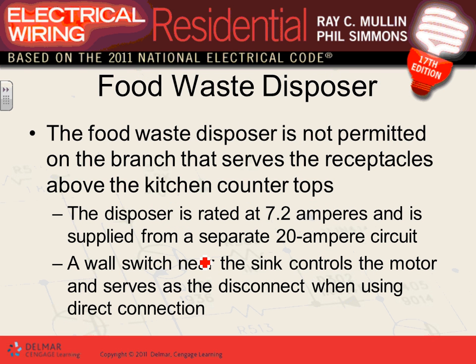Okay. Food disposal. Here's a typical amp rating for these babies. Typically, they are horsepower motors. So this is what you're looking at: typical amps for a garbage disposal, a typical branch circuit for the garbage disposal. That's exactly what you guys did with me. So if you don't know anything about a garbage disposal in a dwelling, 20 amp circuit, number 12, dedicated circuit for the garbage disposal. Done, check, right? Now, if they tell you more information about it, then you can size it. But typically, a 20 amp circuit. So I have my 20 amp circuit.